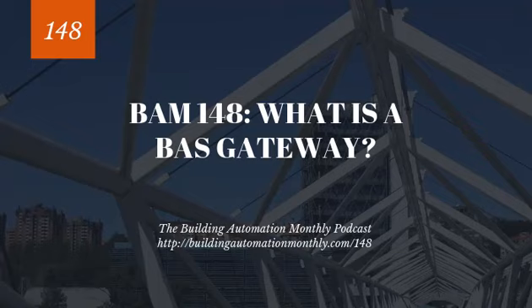So physical gateways are often protocol independent. What that means is that they are not often specific to a protocol. MSTP can travel over RS-485, but Modbus RTU can also travel over 485. So just because it is shielded twisted pair does not necessarily mean it is a specific protocol. That is something I see a lot of folks make a mistake on.